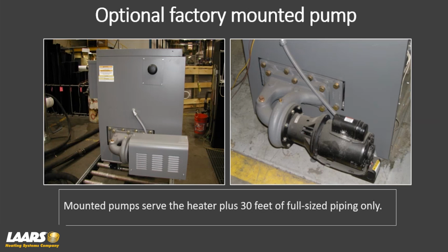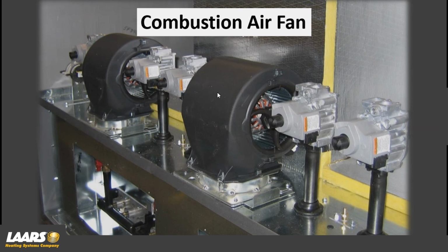If you have further distances, please reach out to applications and they will help you size the piping for additional footage. Now, combustion air fans. These fans have two sets of windings in them. Hypothetically, if I'm going to run the left half of the boiler, this blower will come on at full speed.